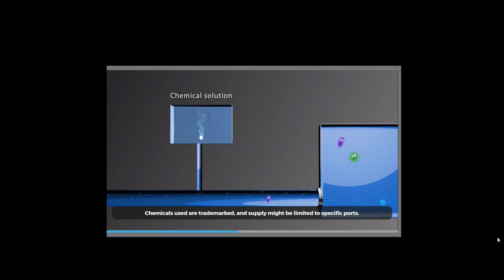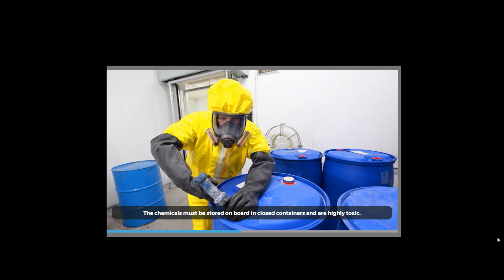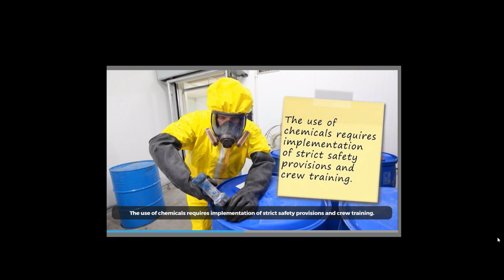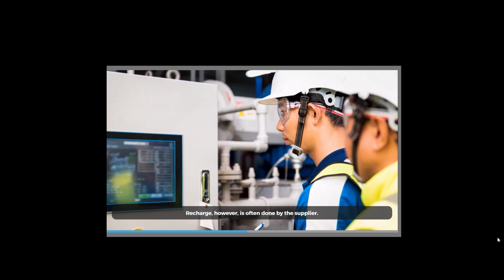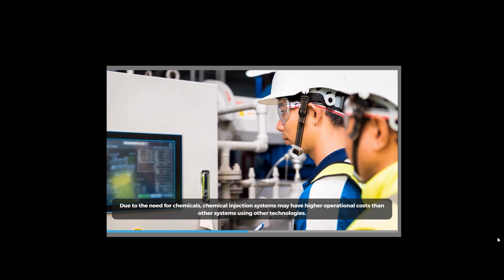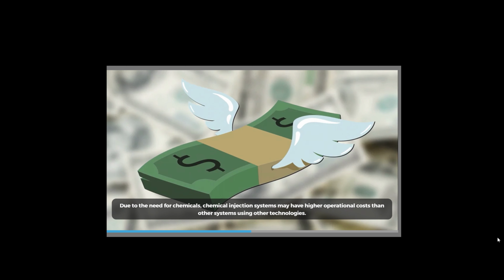Chemicals used are trademarked, and supply might be limited to specific ports. The chemicals must be stored on board in closed containers and are highly toxic. The use of chemicals requires implementation of strict safety provisions and crew training. Recharge, however, is often done by the supplier. Due to the need for chemicals, chemical injection systems may have higher operational costs than other systems using other technologies.